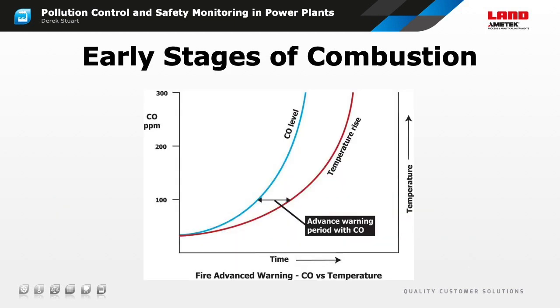This illustration shows schematically what happens as spontaneous heating begins and progresses. Large amounts of CO are produced by the inefficient oxidation associated with spontaneous combustion. Now, ambient air contains very low concentrations of CO, usually well below 10 ppm, so a significantly higher concentration provides a fast and highly specific indication that unwanted oxidation is occurring. As time goes on, there will be enough heat buildup to give an observable temperature rise, and this is also a clear indication that something bad is happening to the fuel.